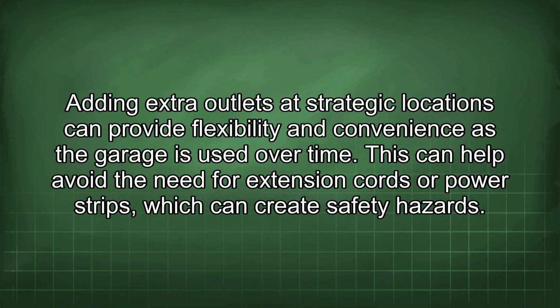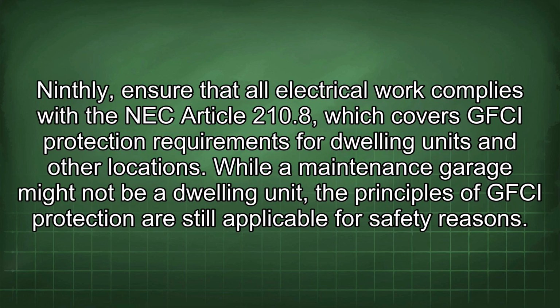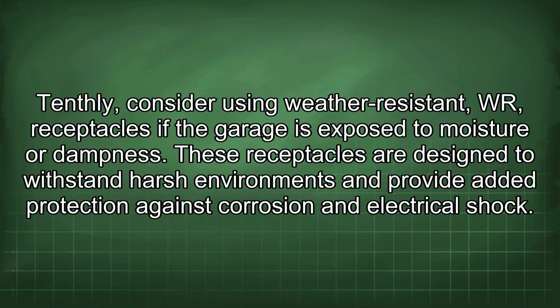Adding extra outlets at strategic locations can provide flexibility and convenience as the garage is used over time. This can help avoid the need for extension cords or power strips, which can create safety hazards. Ninthly, ensure that all electrical work complies with the NEC Article 210.8, which covers GFCI protection requirements for dwelling units and other locations. While a maintenance garage might not be a dwelling unit, the principles of GFCI protection are still applicable for safety reasons. Tenthly, consider using weather-resistant (WR) receptacles if the garage is exposed to moisture or dampness.